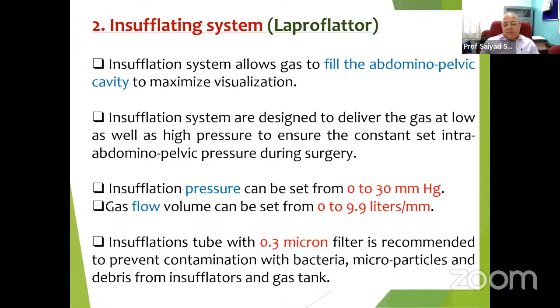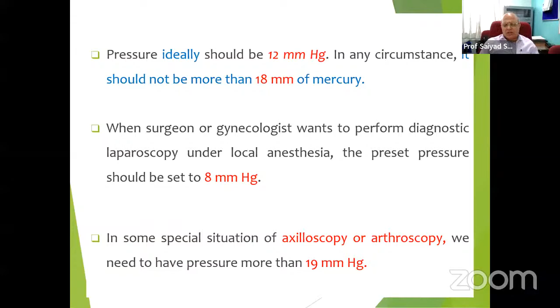A filter is recommended to prevent contamination with bacteria, microparticles, and debris from the insufflators and gas tanks. Now, the ideal pressure should be 12 mmHg. In any circumstances, it should not be more than 18 mmHg of pressure. That is a very, very important thing. When surgeons or gynecologists want to perform a diagnostic procedure, the pressure should be 8 mmHg. In special situations, other surgery, axilloscopy, arthroscopy, you can increase the pressure up to 19 or more than 19 mmHg.